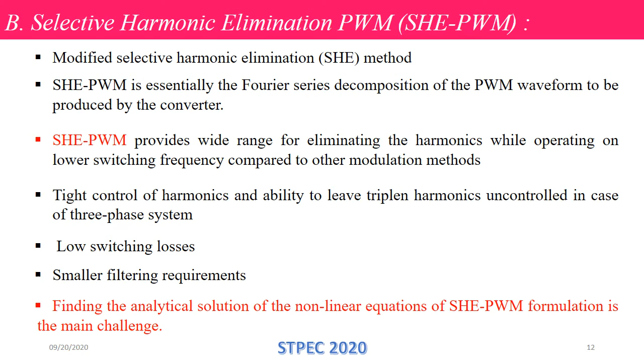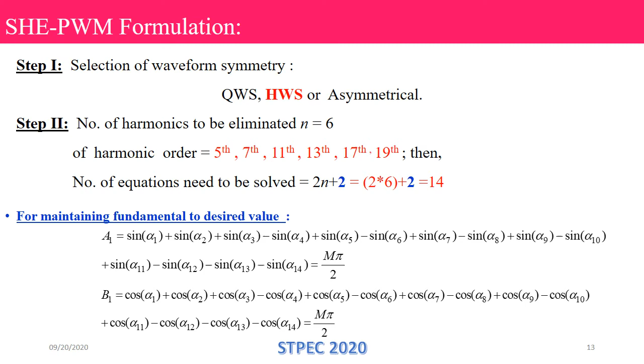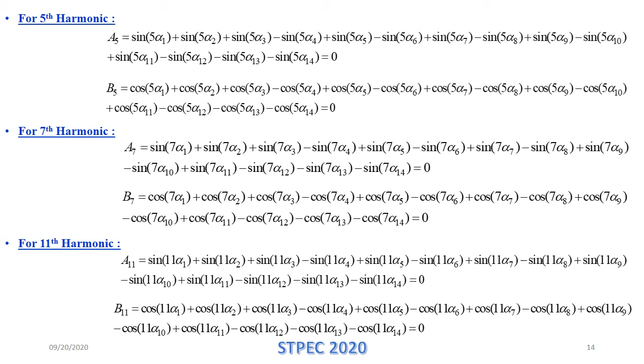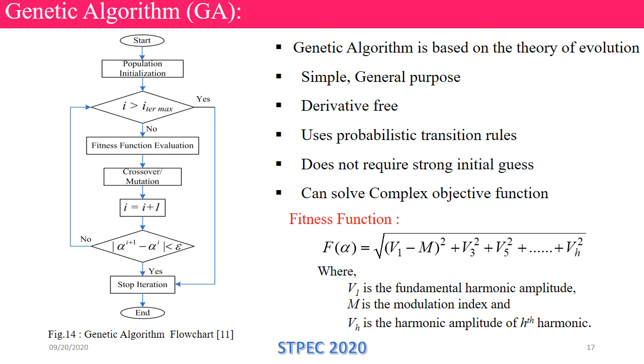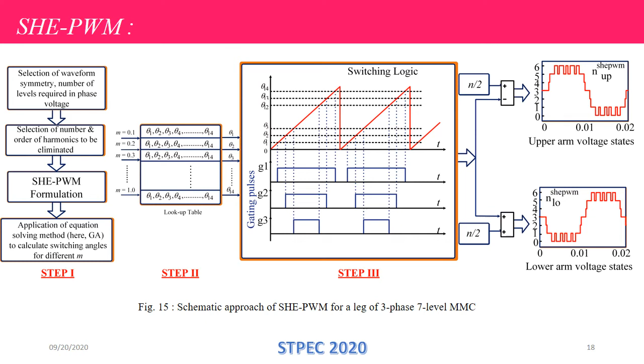Step 1 for SHE-PWM formulation is selection of waveform symmetry. Step 2 is the number of harmonics to be eliminated. Here we have chosen 6 lower order non-triplen harmonics, which are 5, 7, 11, 13, 17 and 19. So a total of 14 equations need to be solved: 2 equations for maintaining the fundamental at the desired value and 12 equations for maintaining the harmonics at 0 level. Genetic algorithm is used to calculate the switching angles from those 14 nonlinear transcendental equations. This is a schematic approach for SHE-PWM of a 3-phase 7-level MMC.